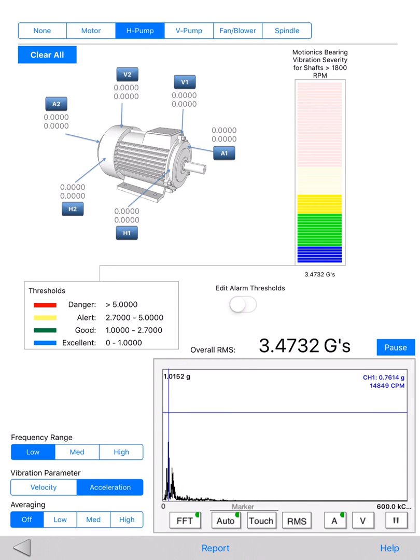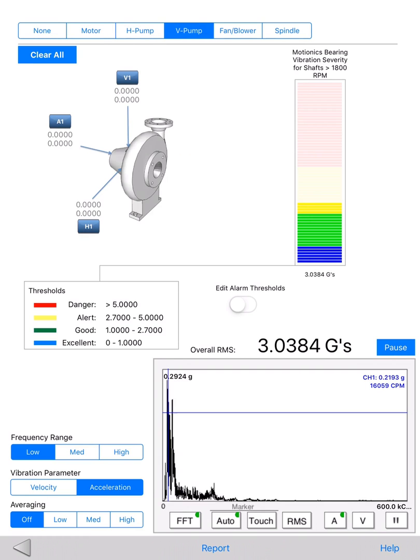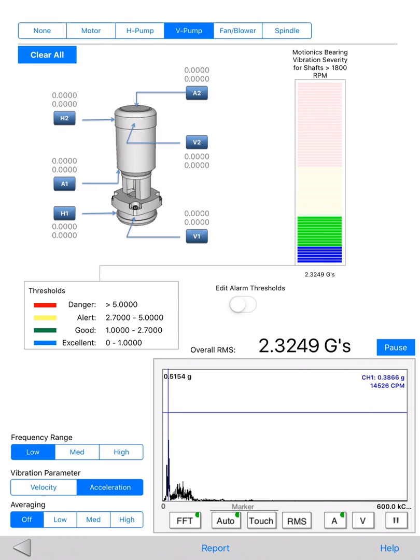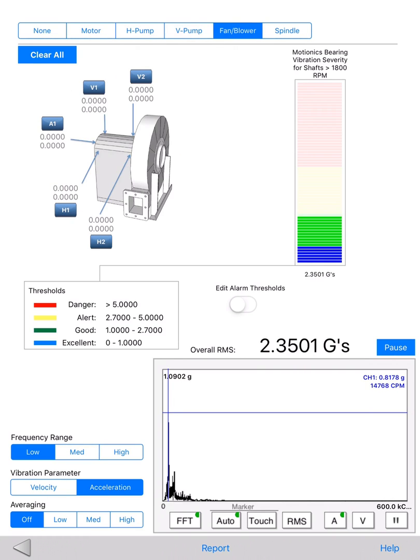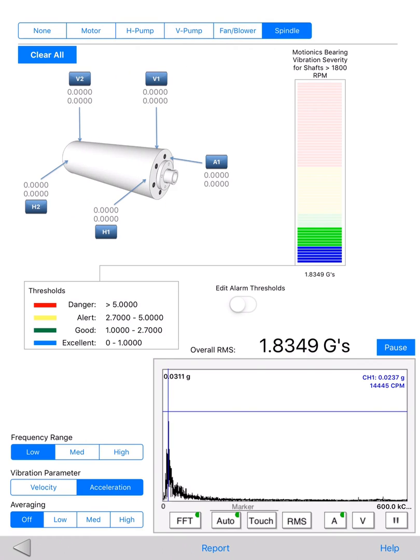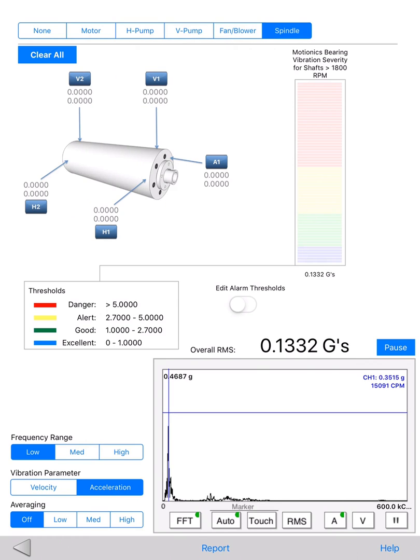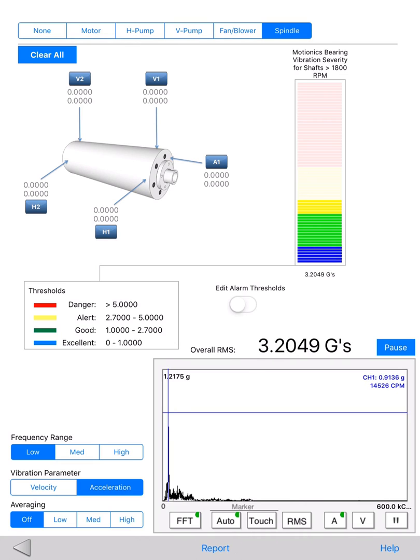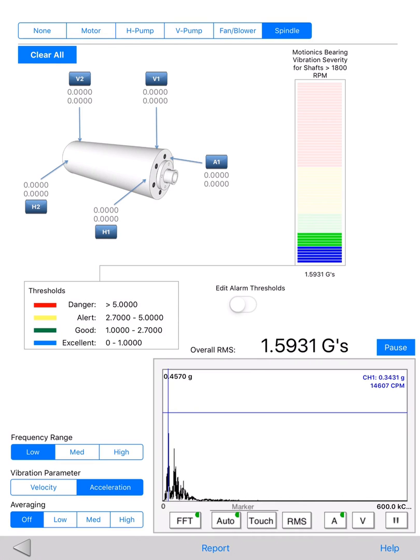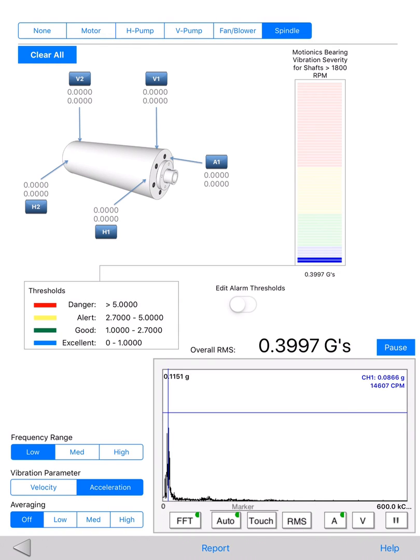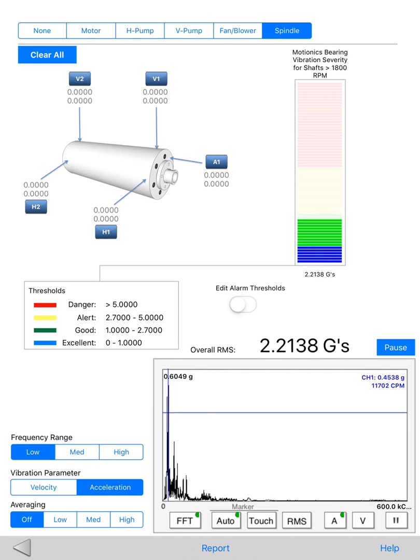including motor, horizontal pump, vertical pump, fan blower, and spindle. For each option the user selects, there will be a corresponding machine graph with marked test points. The user can follow the graphic illustration, place the accelerometer at marked locations, and quickly capture overall vibration readings simply by tapping on the buttons.